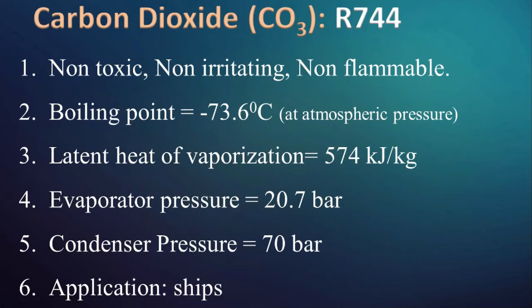Carbon dioxide is a non-toxic, non-irritating and non-flammable gas. It has a boiling point of minus 73.6 degree Celsius at atmospheric pressure. Because of this very low boiling point, for evaporation at minus 15 degree Celsius, we need a pressure of 20.7 bar in the evaporator, and for condensation at 30 degree Celsius, we need 70 bar pressure in the condenser, which is very high. Hence, the system has to work under high pressure and it makes it less efficient.